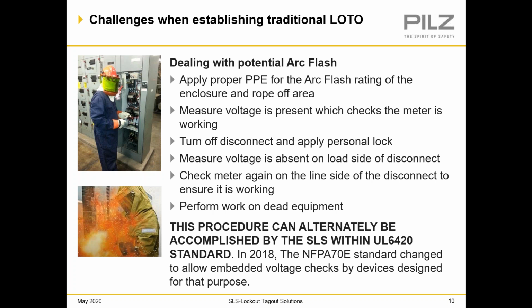And that may be the dead equipment that actually is just the panel itself, going inside there and doing work, or the zone that the panel is providing power to. If you've done a lockout procedure and you're locked out and you've measured voltage and there's no voltage available, all that procedure can be alternately accomplished using the SLS system that we have within the UL 6420 standard. And in 2018, the NFPA 70E standard changed to allow embedded voltage checks by devices designed specifically for that purpose. So all of this procedural stuff here with traditional lockout can be replaced by pretty much an automatic procedure within the SLS design.